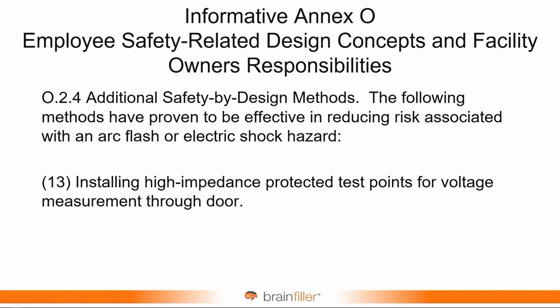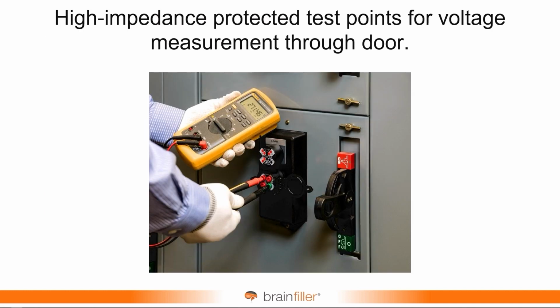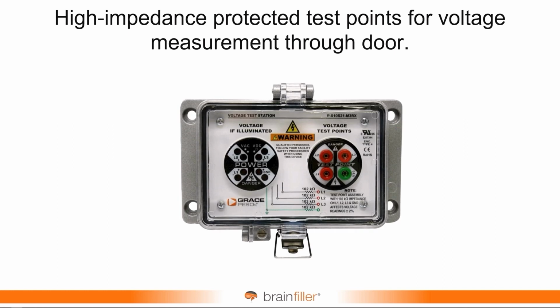There are many, many informative annexes, and I just wanted to point out a couple of things here. Informative Annex O, employee safety-related design concepts and facility owners' responsibilities. There was a list, additional safety by design methods, and there's a new item added to the list, and that is installing high impedance protective test points for voltage measurement through the door, such as this type of device. You have a test point that is through the door, so that way you can measure absence of voltage without exposing yourself directly to the equipment by opening up the enclosure.